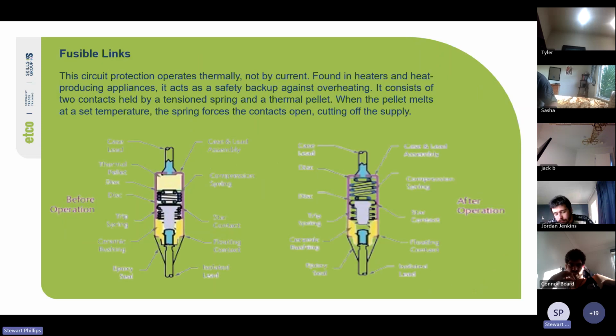Cool. And then you've got your fusible link. So the circuit protection operates thermally, not by current, found in heaters and heat producing appliances. It acts as a safety backup against overheating. It consists of two contacts held by a tension spring and a thermal pellet. When the pellet melts at a set temperature, the spring forces the contacts open, cutting off the supply.